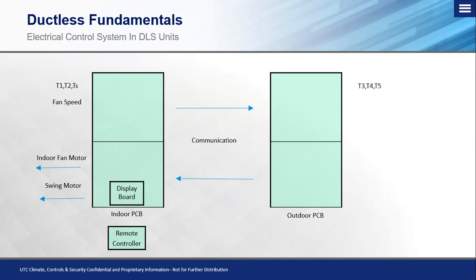Now, in your outdoor unit, you have your three main sensors. We know those as the outdoor coil, outdoor air, and compressor discharge, which is T3, T4, and T5 sensors. Okay, that information is fed into the outdoor board, and through the communication line on the signal wire, the information for return air, coil temperature, and the setting by the remote controller is transferred to that outdoor board. So the outdoor board, or the brains of the operation, knows what's going on with its indoor or indoor units, depending on what type of system that you have. Okay. In turn, it's going to make logical decisions such as changing the positions of the EXV or the EEV or the expansion valve, changes to your compressor speed, changes to your outdoor fan motor, and then also changes to your four-way valve, of course, depending on which mode you're in, whether that be heating, cooling, or if the system is off.